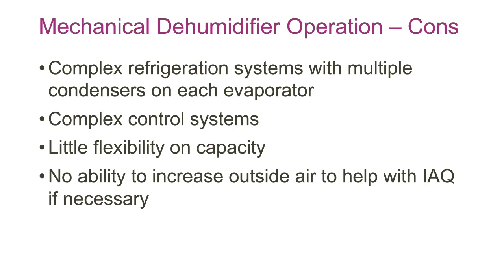If you undersized one, you're kind of stuck. You've got a 40-ton unit, it's going to do 40 tons, and if it happens that your evaporation rate is wrong, you're going to be in trouble. And also then if they change conditions with the water a little bit, it'll be a challenge, and they don't really have an ability to increase the amount of fresh air or condition it if after you're installed you're having indoor air quality challenges.